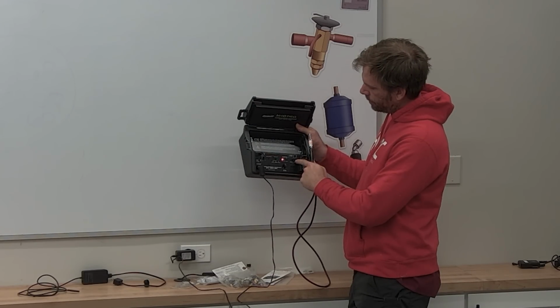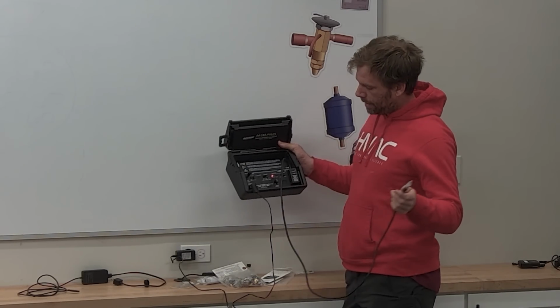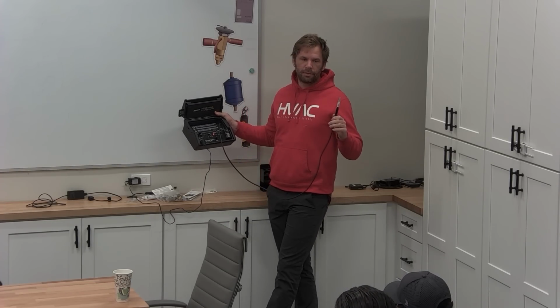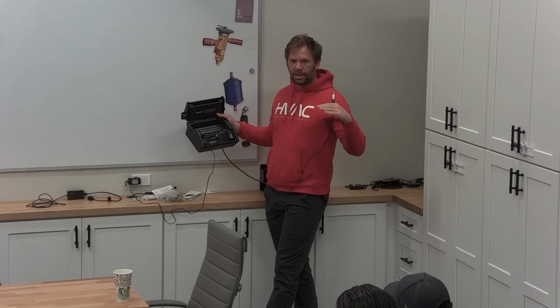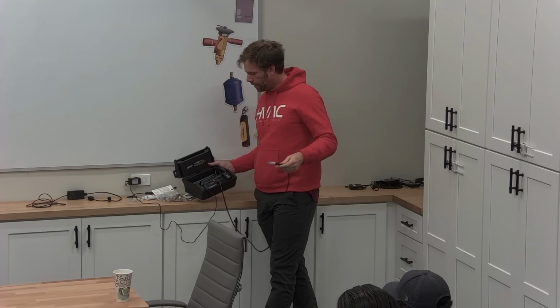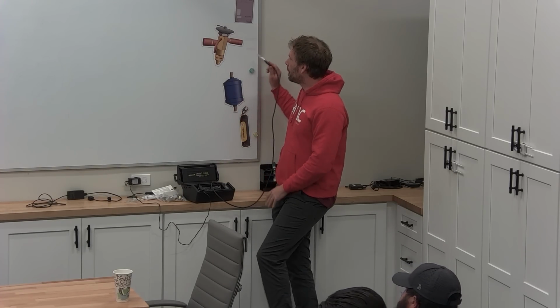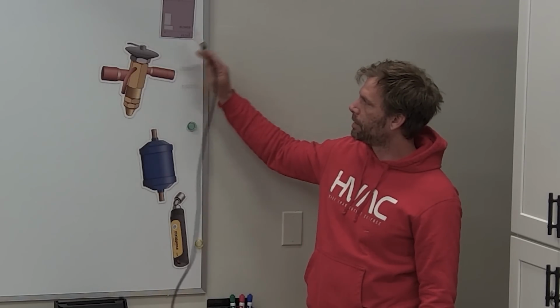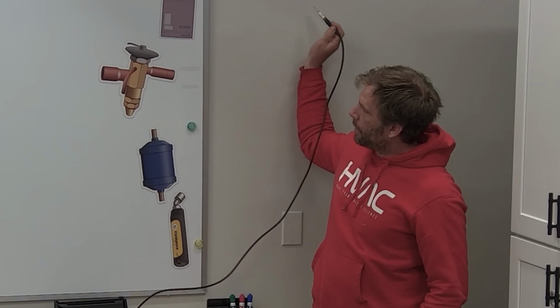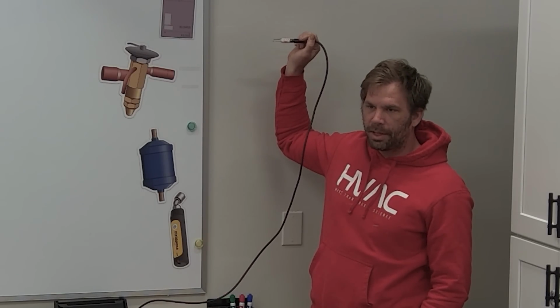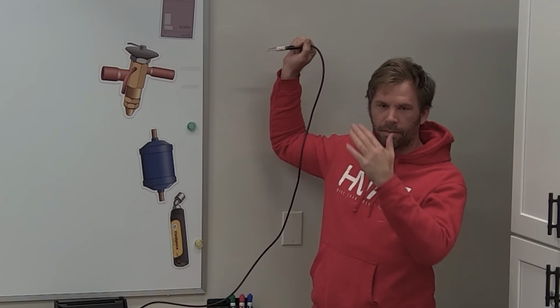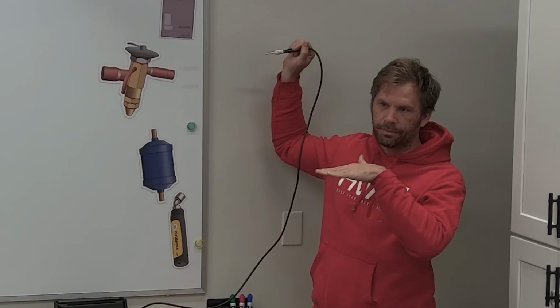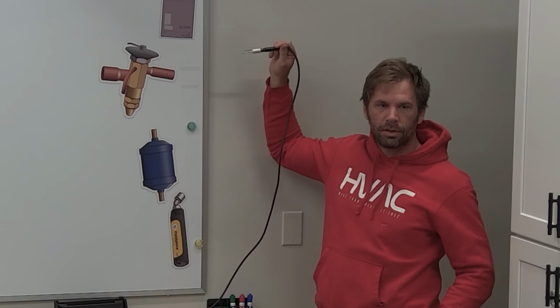You switch it to auto, and whatever background refrigerant level you have, it'll set that as its baseline. So as soon as you put it into auto mode, this is the baseline, which right now is no refrigerant. But if you have a lot of refrigerant in an area, you switch it to auto, that'll be your new baseline. So if you're coming along in auto mode, let's say we're leaking out of the end of this TXV port. I switch it to auto and I'm getting hits out here. After a little while, I'm going to stop getting hits. In auto, it's constantly readjusting that baseline. So now I'm going to stop getting hits here, even though there's refrigerant.